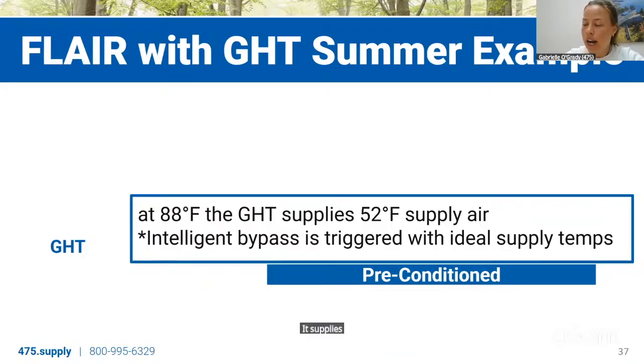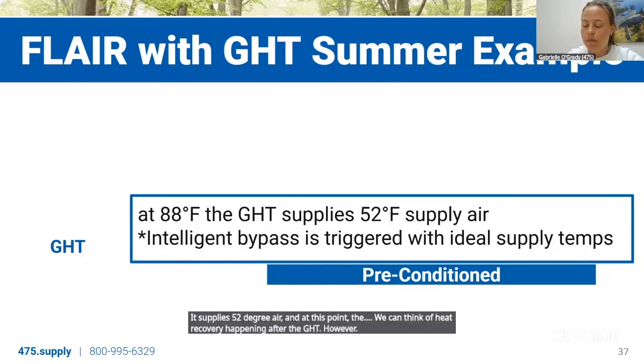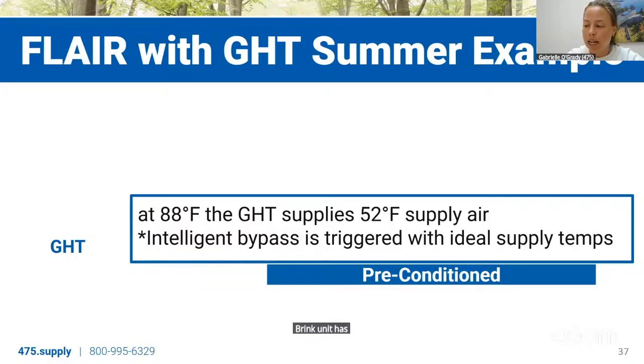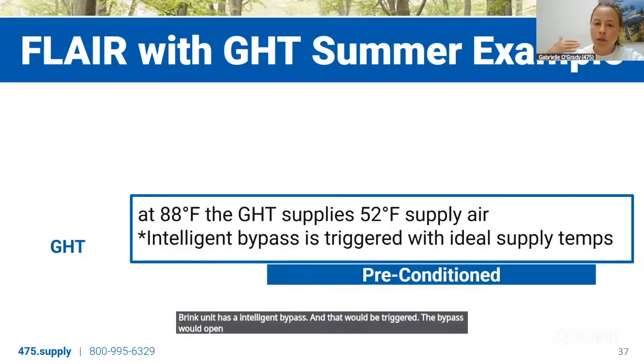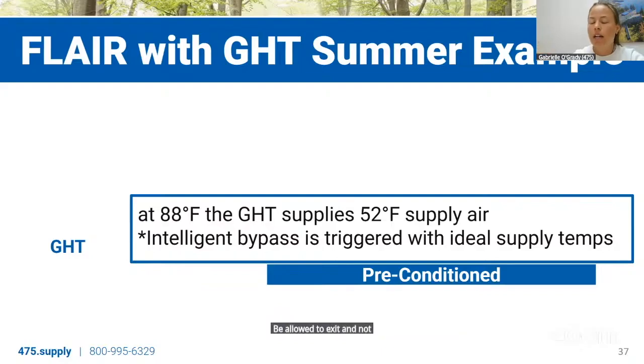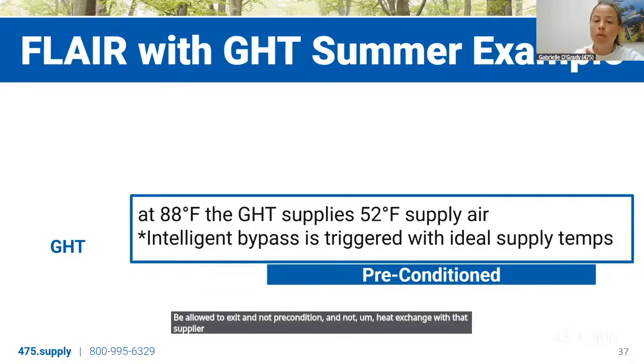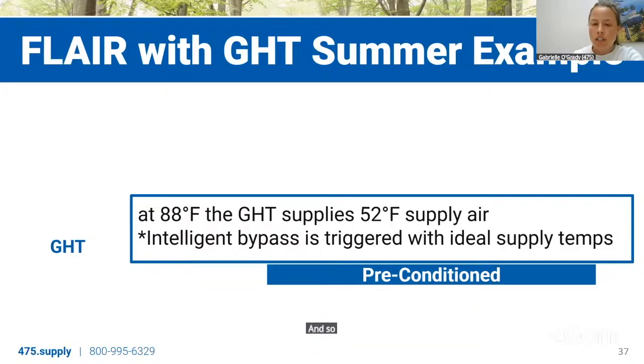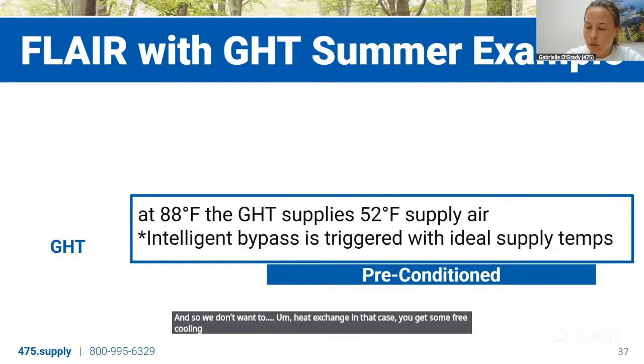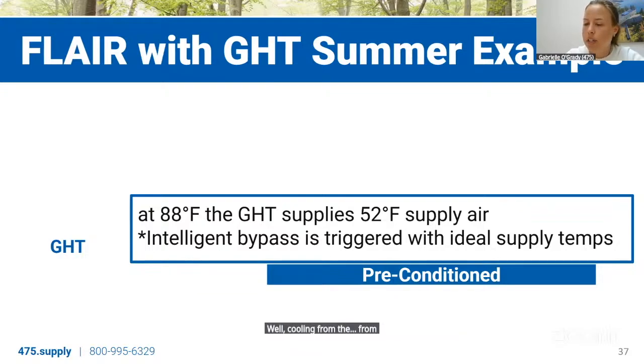Supplies 52 degree air, and at this point, we can think of heat recovery happening after the GHT. However, the Brink unit has an intelligent bypass, and that would be triggered. The bypass would open, and that exhaust air would just be allowed to exit, not preconditioning and not heat exchanging with that supply, because we know the supply is actually going to be cooler than what's in your home. And so we don't want to heat exchange. In that case, you get some free cooling from the ground here with the GHT system.